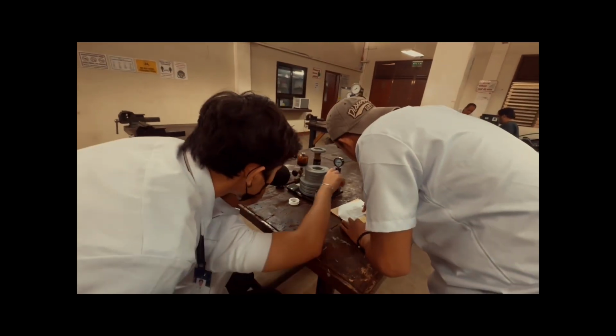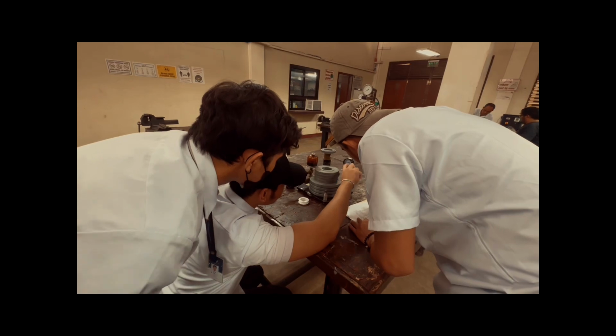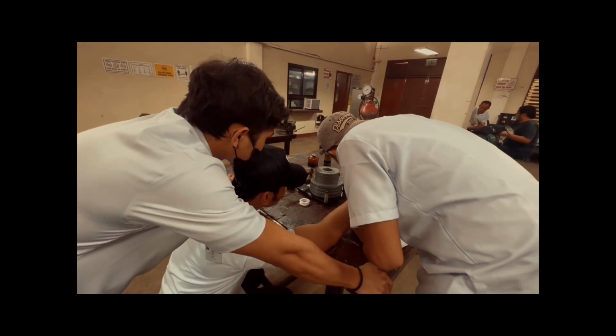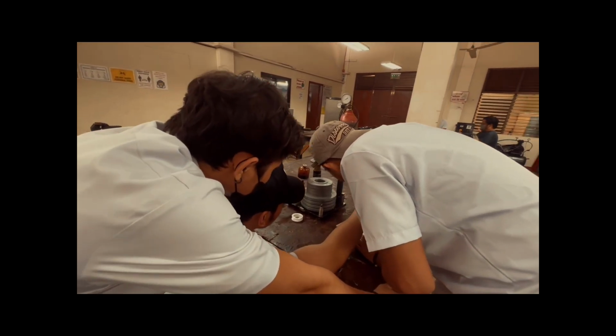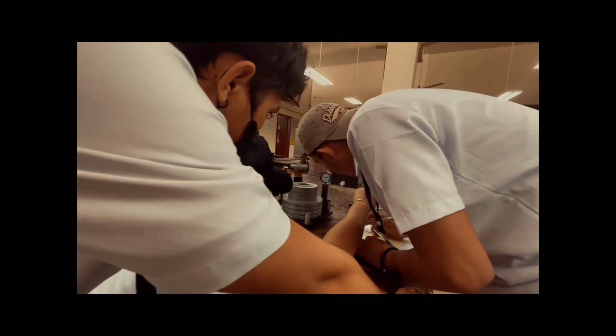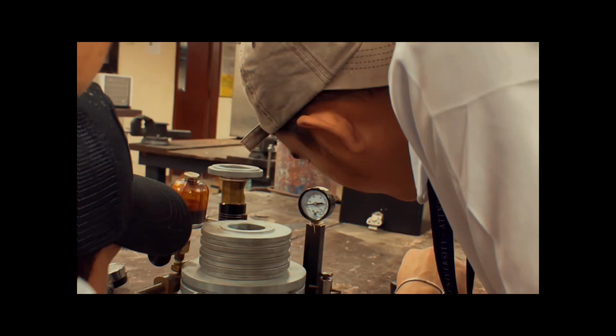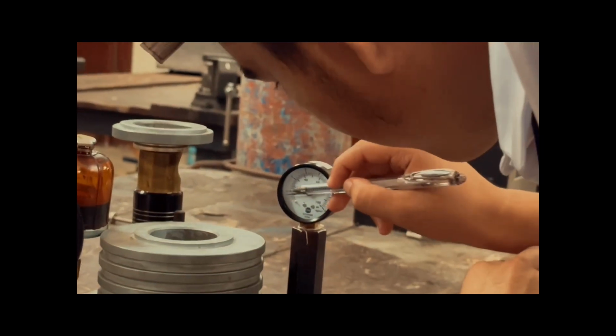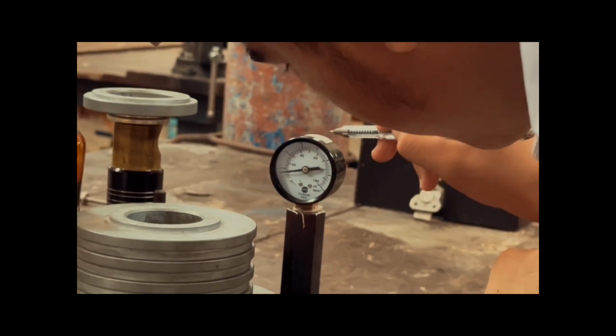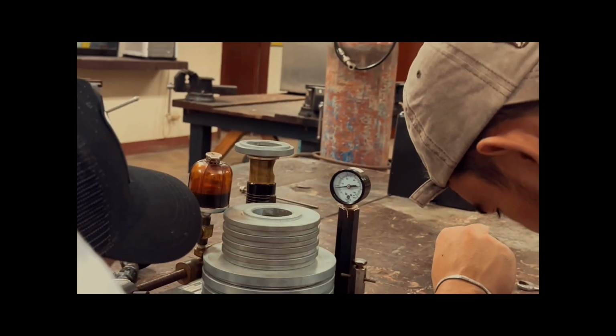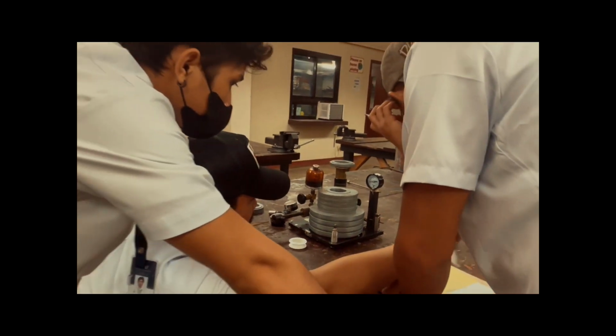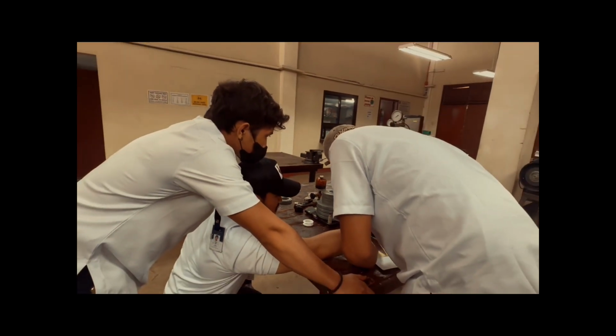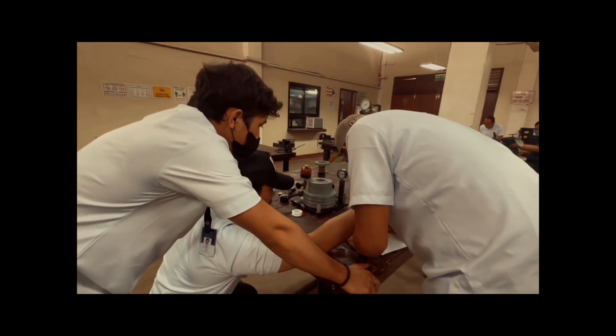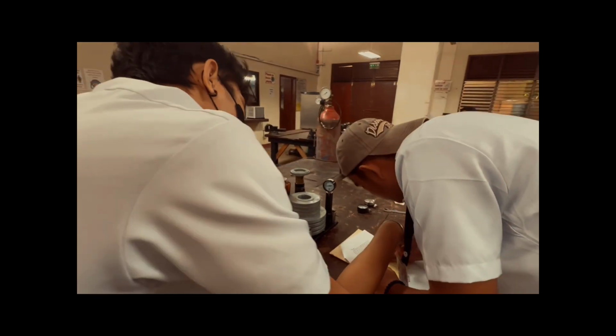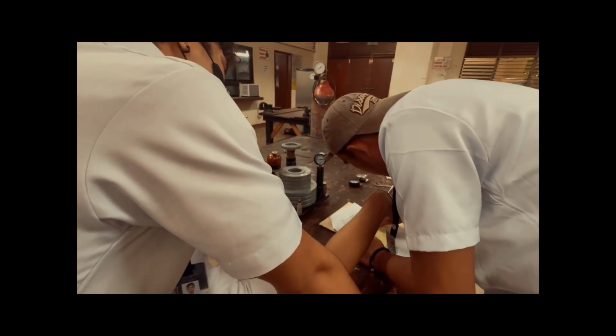For calibration, carefully connect the pressure gauge to the dead weight tester. The pressure gauge we use is the 100 psi gauge, and then gradually apply pressure using the weights while closely monitoring the pressure gauge readings. For each weight added, record the applied pressure and the corresponding reading on the pressure gauge. Ensure the pressure stabilizes before recording the readings.